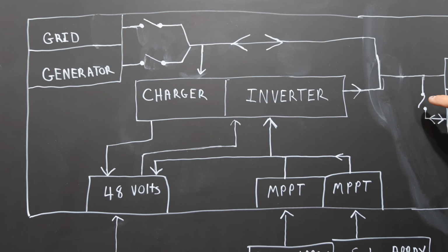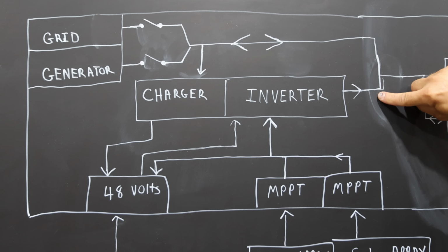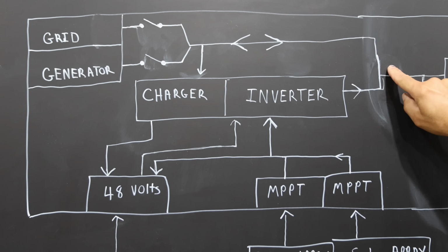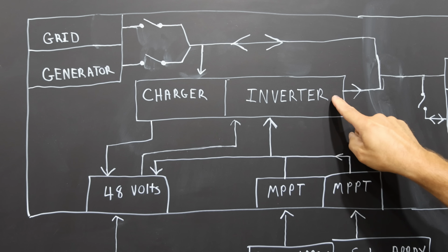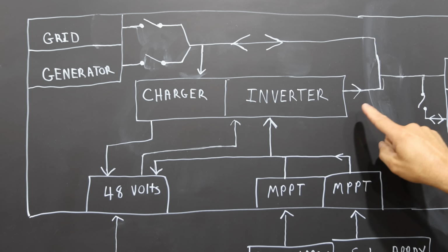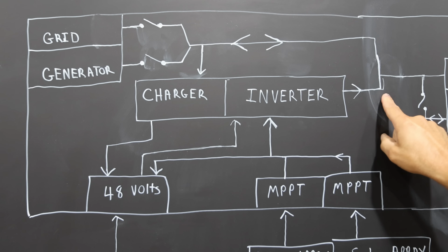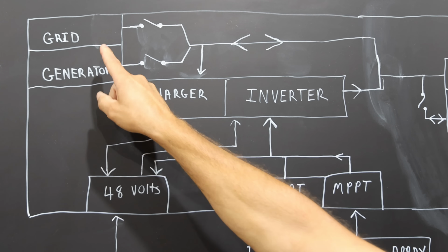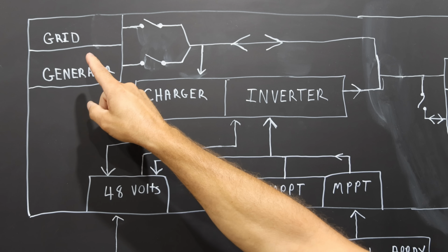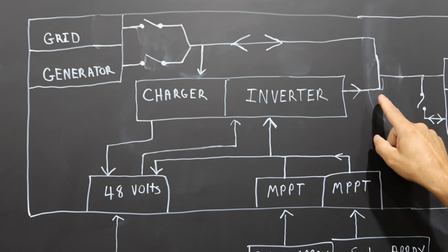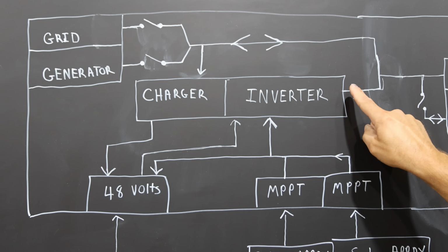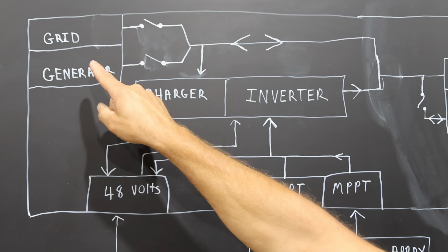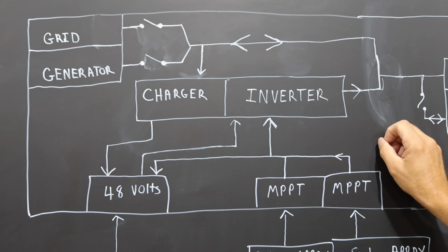So the big difference is on the off-grid inverter there was a transfer switch, and it could switch between inverter power or grid power for what was going to the output. Now that's all gone. The inverter is physically tied to the grid connection, thus grid tied, and the inverter syncs up with the grid. So it matches the waveform and the voltage, and then it's in sync with the grid, so then power can either flow out of the inverter to the output, but it can also flow backwards to the grid to sell back and zero the meter.